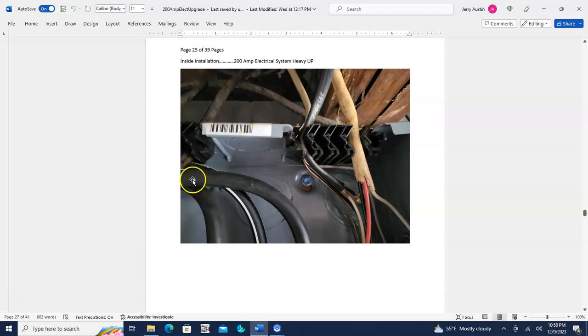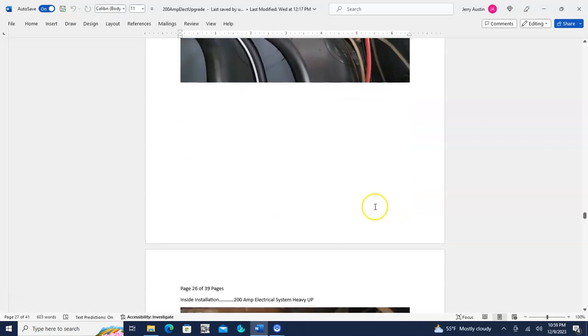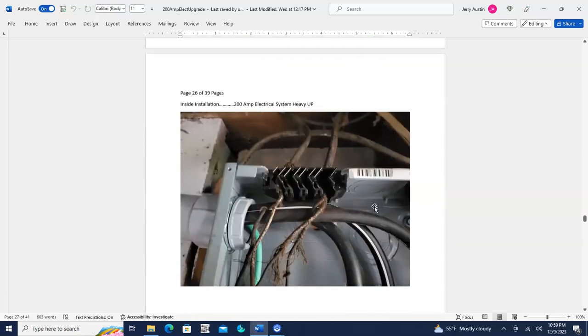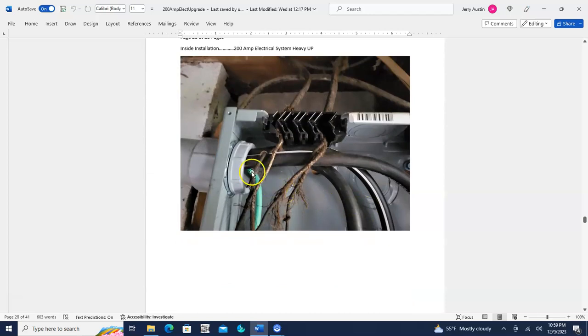These are power leads coming into the box. That's one electrical power lead, the other electrical power lead, and this right here is the ground lead for the power. And these are a couple of circuits coming into the box. More of the same. Here you see the leads I was telling you about. One power lead, the other power lead, the electrical ground, and this is the safety ground, the green wire safety ground.